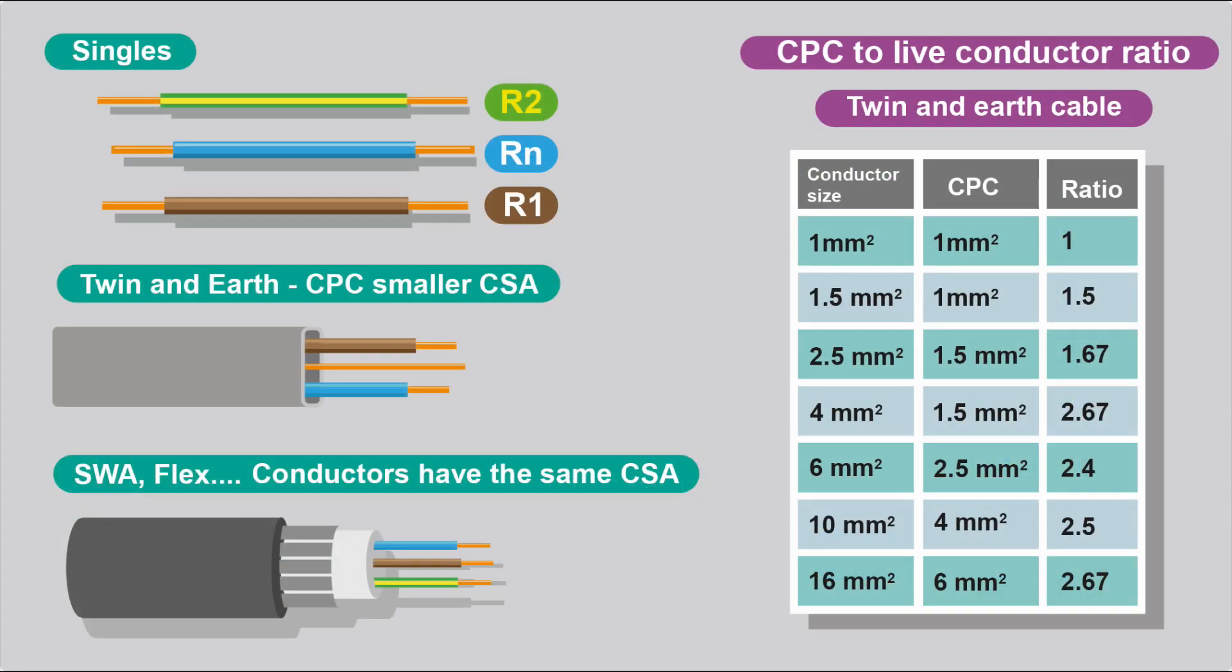Remember we've got a milliohm per meter reading for each conductor size. Now, sometimes the conductors in the cable aren't the same size. If you're using singles, you generally use the same size conductors, and in flex and SWA, the conductors usually have the same cross-sectional area. But in twin-and-earth, the CPC has a smaller cross-sectional area than the live conductors, the line and the neutral.